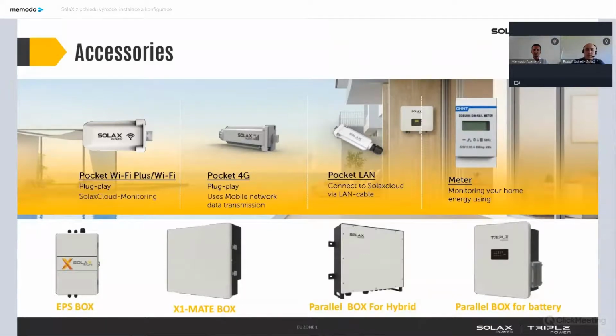I already mentioned some of these accessories, which you can see here on this slide below. The EPS box, for example, is necessary for automatic switching. So in case of a blackout, for example, when you have an EPS box installed, the EPS box interrupts the connection to the public grid, so that the inverter can run in off-grid mode and give EPS power, or emergency power supply, to the house of the customer. Basically with the EPS box, it is possible to cover the EPS mode for the whole house installation.